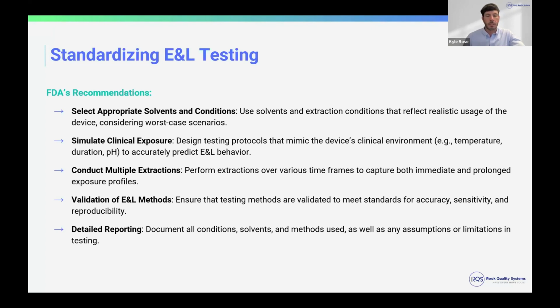and then having detailed reporting for this. So just like everything else with your device testing or your biocompatibility testing, the majority of this chemical analysis is going to be done by an external lab. You'll have to work with them to identify what tests apply to your device, what the conditions of the testing are, and then make sure that they have the correct protocols in place, the equipment and methods are validated, and then also that you get this report that you can then share with the FDA with your FDA submission.